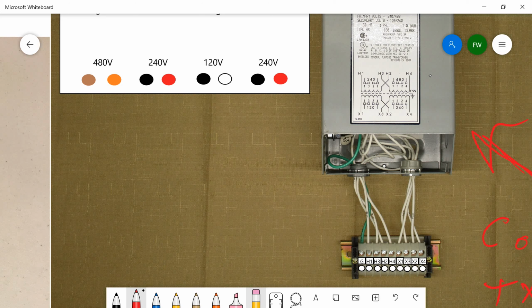You can do 480 or 240. 208 volts will work okay as well. Each winding is capable of holding 240 volts. So if you need to do high voltage, it's just a matter of jumpering H3 and H2 together. But let's pretend if you had low voltage, you'd run that in parallel. So then you would run H1 to H3 and H2 to H4, and then you bring your L1 and L2 coming in, and that would give you your output voltage, which in this particular case is going to be 120, typically is for most control circuits. And this one here, we have a split winding on the secondary as well, so we'd have to parallel this. So we're going to hook up X1 to X3 and X2 to X4, and then that will give our 120 volts coming out.